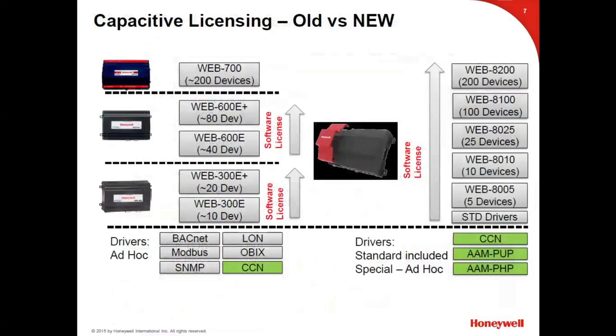Here's a slide comparing the old AX JACEs to the new JACE 8000. In the old days, if you added devices to a Web 300, you'd have to replace hardware — go from a Web 300 to a Web 600. The 300 might be fully functional, but it didn't have the capacity. Those issues are gone with the JACE 8000, released in 2016. The hardware stays in place and you just get a bigger license — you simply add on the license that allows more devices, from 25 up to 200 controllers.